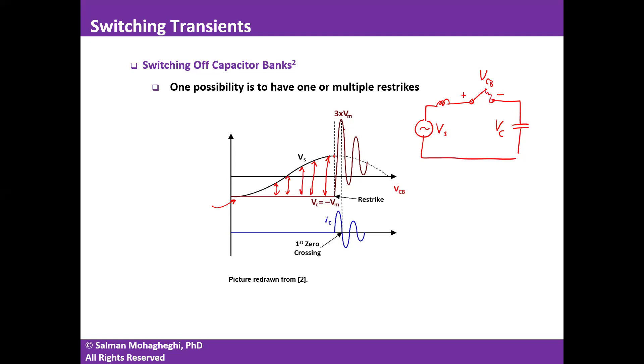When re-strike happens, the capacitor pulls the system voltage toward minus V_M and starts oscillating with a magnitude of 2·V_M. The oscillation carries the capacitor voltage from minus V_M up to 3·V_M. When the current crosses zero and the arc extinguishes, the capacitor is left with a voltage of 3·V_M.